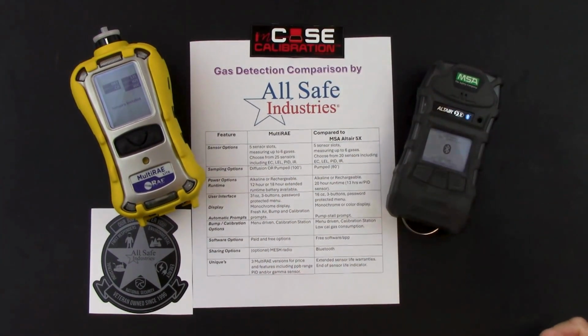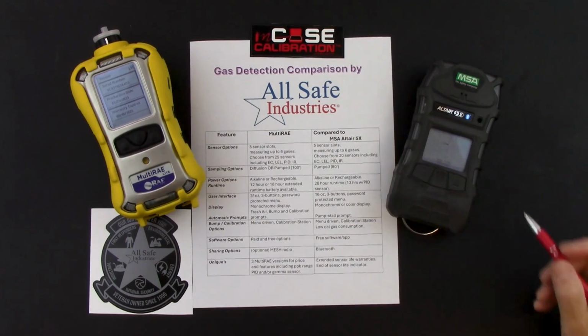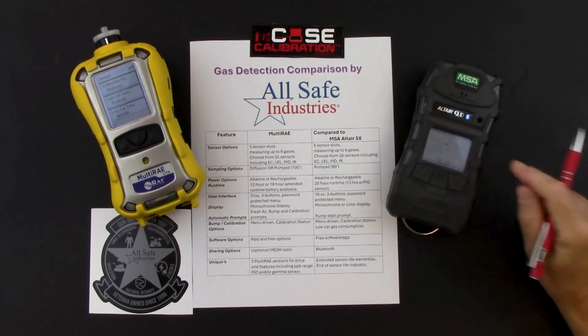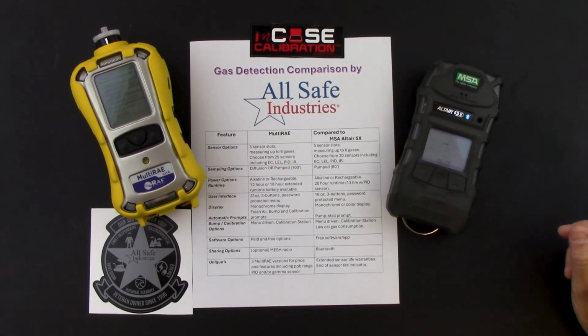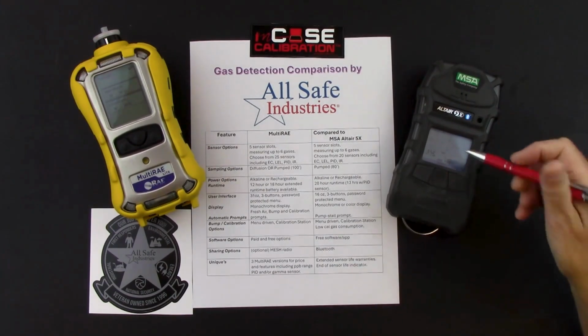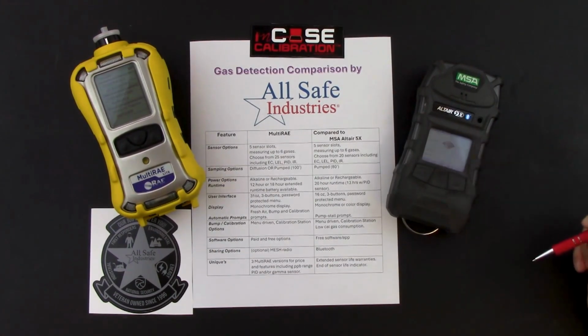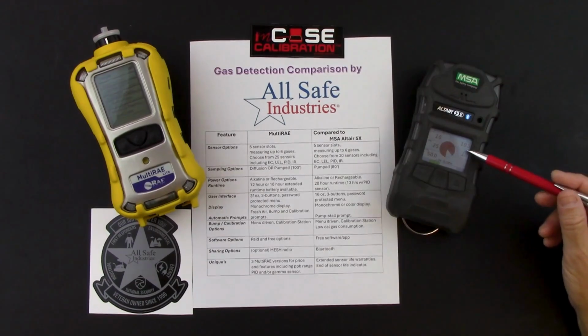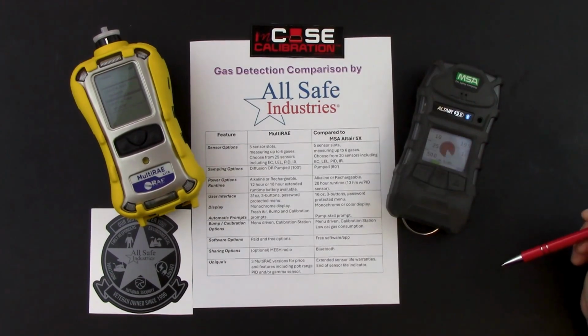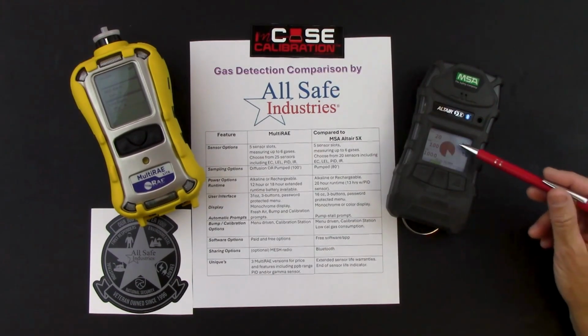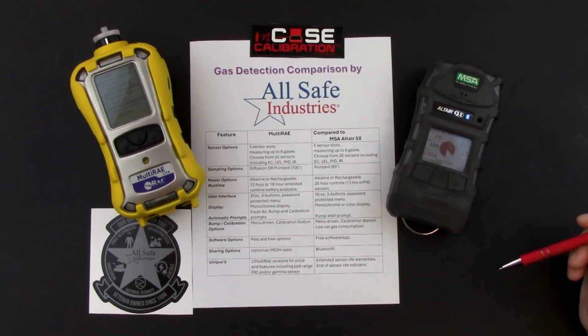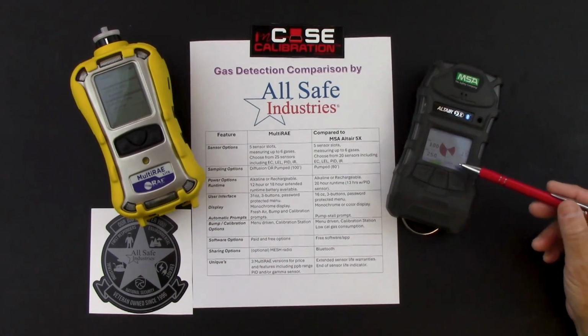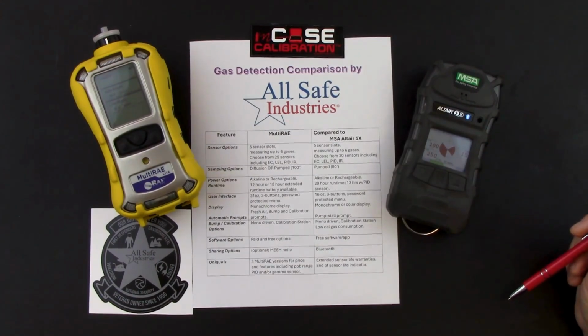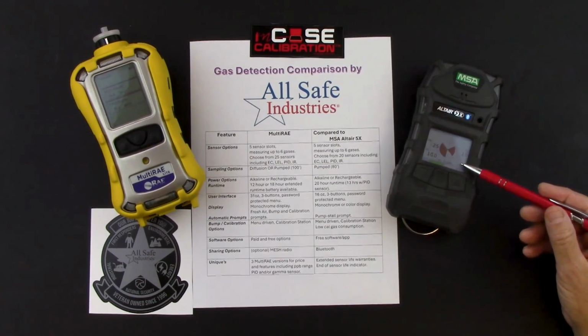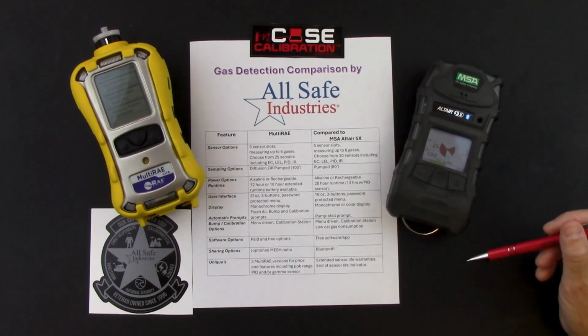Showing me that I have Bluetooth installed, the different gas sensors that are installed. There's my PID sensor measuring VOCs. There's my low alarm set points. There's my high alarm set points on all 5 channels. There's my short-term exposure limit alarms for my toxic sensors. There's my time-weighted average set points for my toxic sensors.